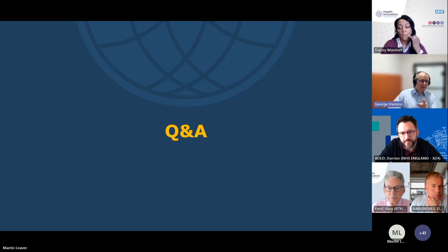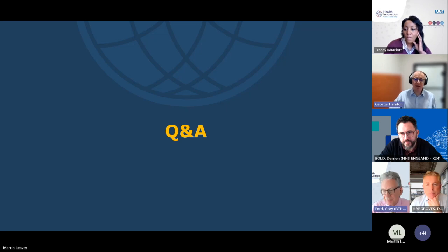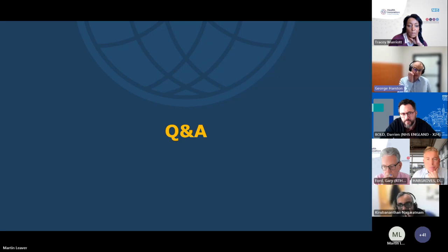Just to pick on the second question, if you want me to answer that about AI. Yeah. So how's the AI software, the output, the quality tracked? And what level of performance is acceptable, and do we track it? So, a really important question for us as a manufacturer, and it really speaks to our post-marketing surveillance activity. So how do we monitor the performance of the software when it's being used in the real world?